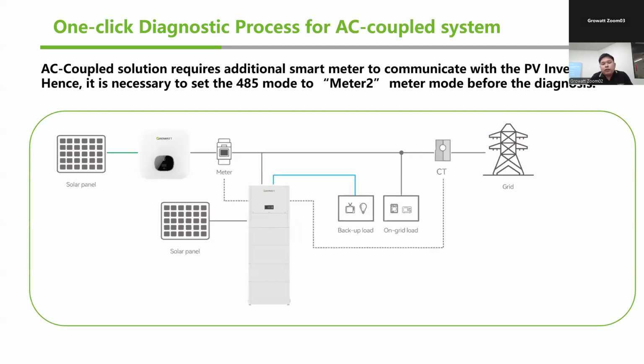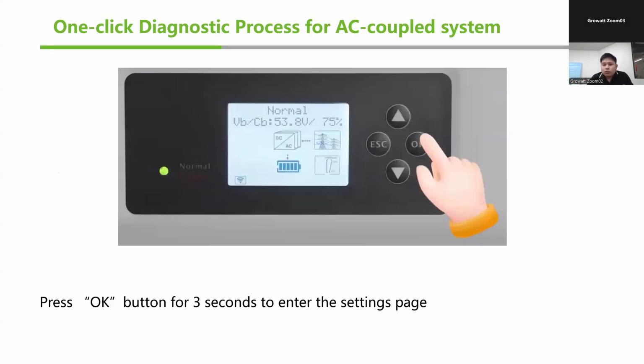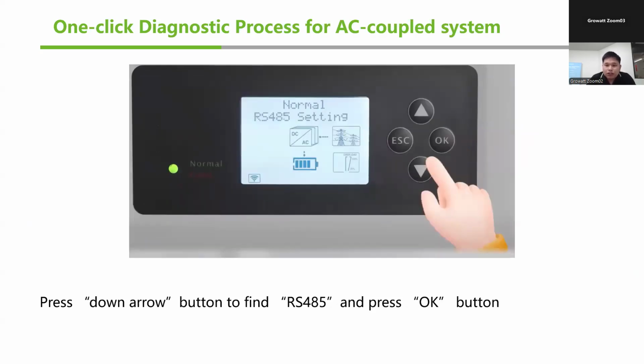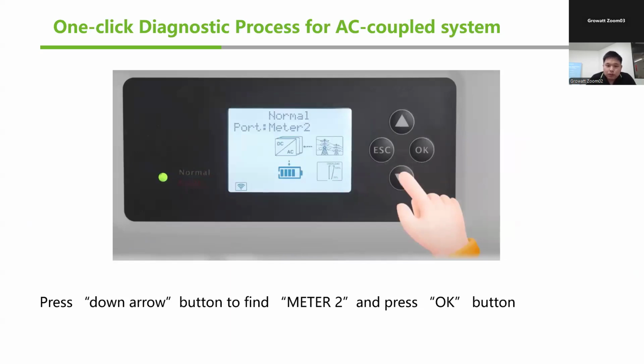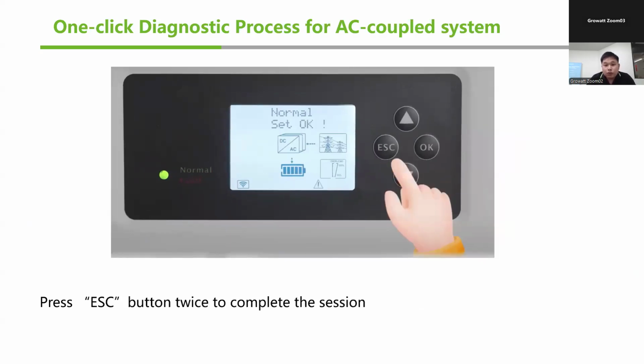Now, in the special cases where this system is installed as an AC coupling system, the only thing that you need to do before running the diagnosis test is to change the 485 mode to meter 2. This is because an external meter has been installed, so we need to change the settings before we proceed to the check. So changing the settings is a very straightforward process. Press OK for more than 3 seconds to enter the settings page. In the settings, just click down continuously until you find the RS485 setting, and then press OK, and then press OK again to go to the meter 2 section. In the port, find meter 2, and then press OK, and then press escape. So that's basically how you set the system if it is under an AC coupling system.